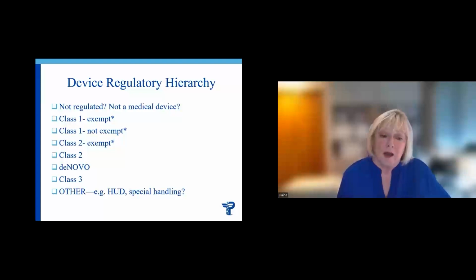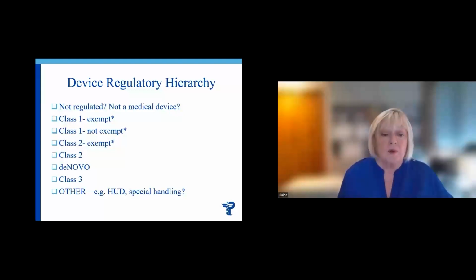But I've been working a lot with Class 1 medical products, which are exempt from 510K. And one of the interesting aspects I find of that is that we tend to be taking new technologies and applying them to Class 1 devices. And that can actually cause a product to be not exempt. But also when FDA went through and exempted all Class 1 devices, they did make some exceptions.